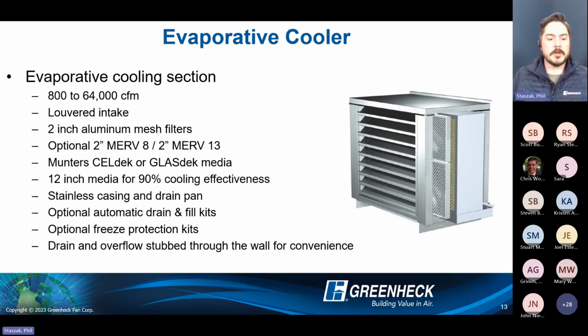So you guys are in a unique market out there in Washington. When you get a little warmer, you're definitely a little less humid. Here in Wisconsin, this type of technology doesn't work. When we get hot, we get very humid, so trying to introduce water to already saturated air does really little to nothing as far as effectiveness.